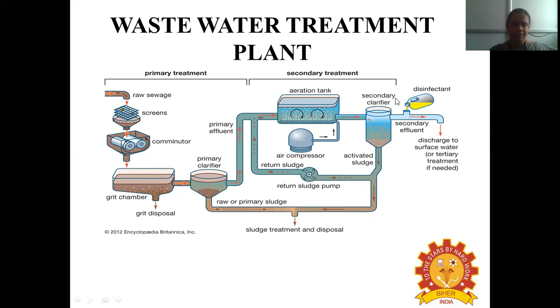The secondary treatment, also called the activated sludge process, receives the primary clarifier effluent. In the aeration tank, oxygen is provided so that microorganisms present in the wastewater are activated and made more active. The aerated effluent then goes to the secondary clarifier, where sludge deposits at the lower layers. Part of this activated sludge is returned to the aeration tank. The secondary effluent then goes to disinfection or advanced tertiary processes.